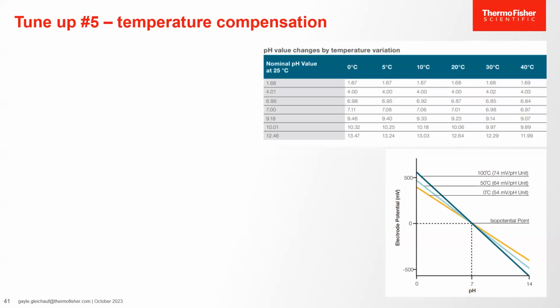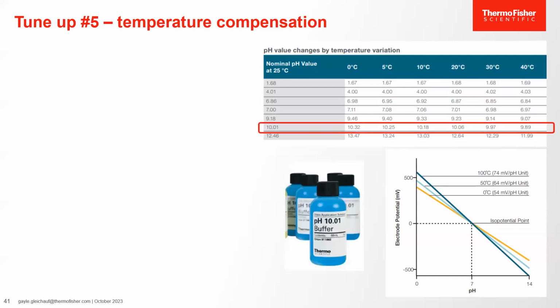Tune-up number 5, temperature compensation. Temperature can change the known values of your calibration buffers, and temperature changes the pH electrode's slope. For example, a pH 10 buffer has a known value of 10.01 at 25 degrees C, but it has a pH of 9.89 at 40 degrees C. The ideal slope of a pH electrode is about 59 millivolts at 25 degrees C, but is about 64 millivolts at 50 degrees C. These examples are why we will want to pay attention to the effects of temperature on our pH calibration and readings.